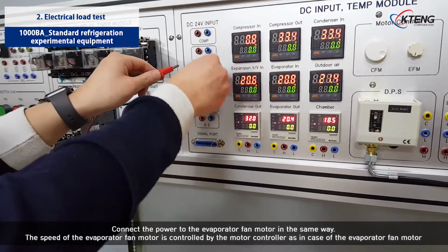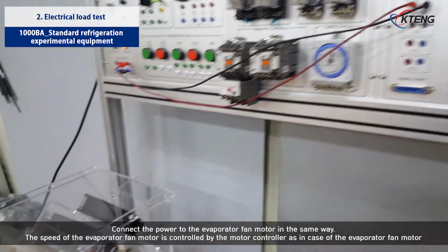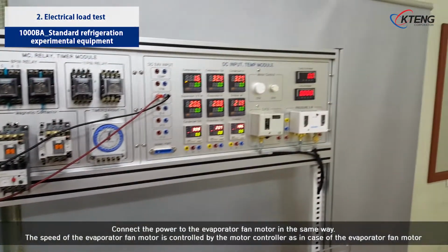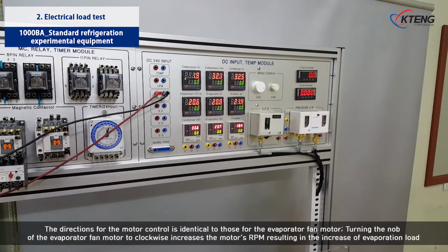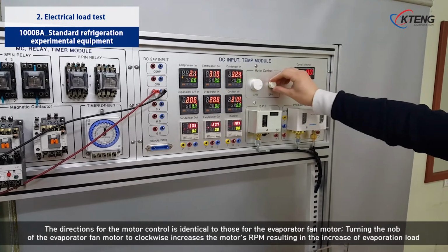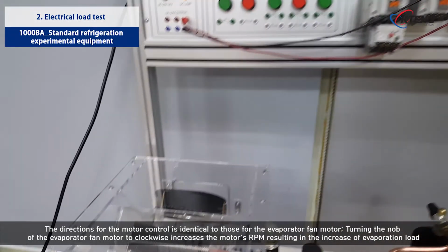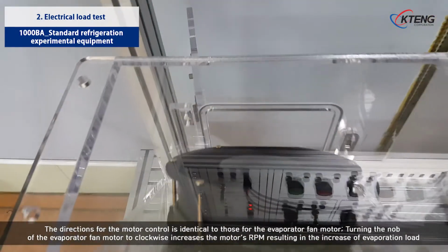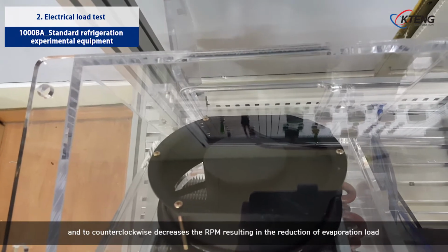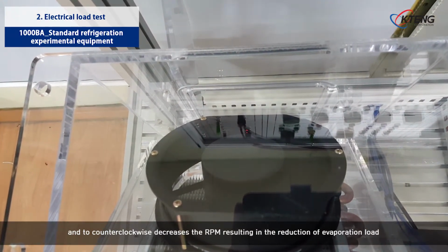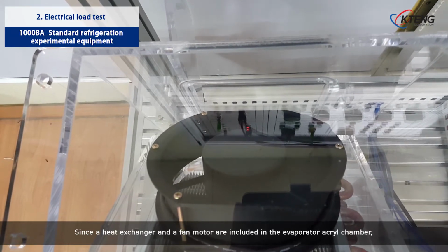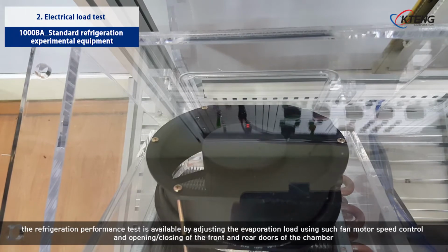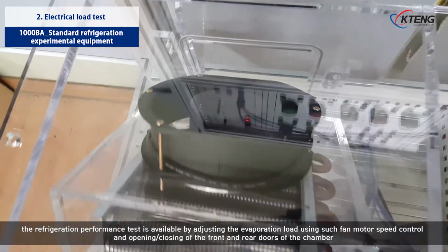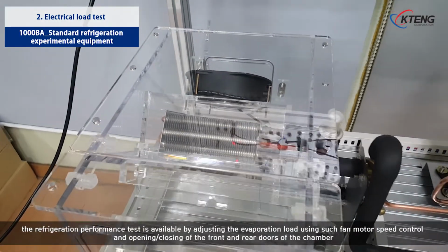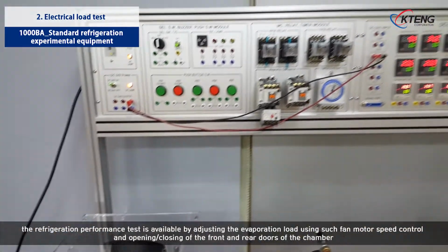Connect the power to the evaporator fan motor in the same way. The speed of the evaporator fan motor is controlled by the motor controller, as in the case of the condenser fan motor. The directions for the motor control are identical to those for the condenser fan motor. Turning the knob of the evaporator fan motor clockwise increases the motor's RPM, resulting in the increase of evaporation load, and counterclockwise decreases the RPM, resulting in the reduction of the evaporation load. Since a heat exchanger and a fan motor are included in the evaporator acrylic chamber, the refrigeration performance test is available by adjusting the evaporation load using such fan motor speed control and opening or closing of the front and rear doors of the chamber.